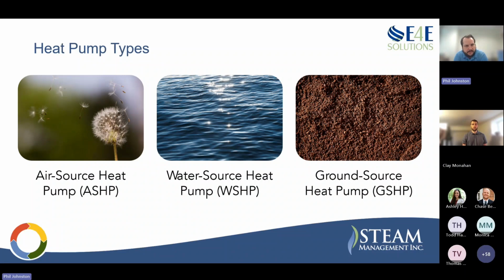When we talk about heat pumps, there are different types. All this really has to do with is where the heat is coming from. Air source is very common because they're usually the easiest to implement. They don't require additional piping or pumping or anything like that. You're just taking the heat out of the air and pushing that heat into some other medium.